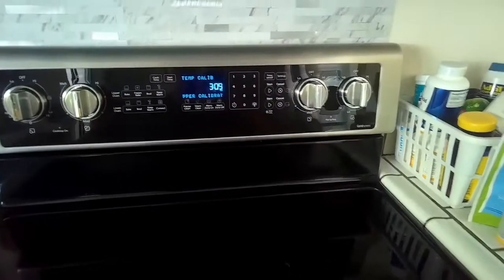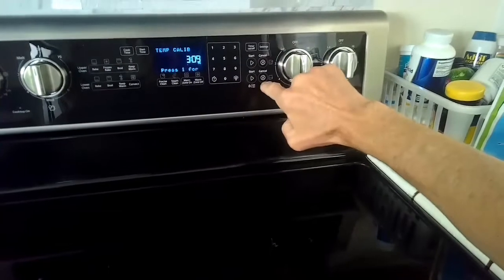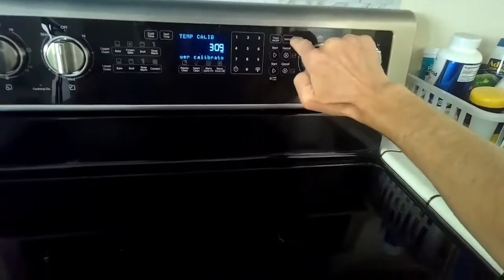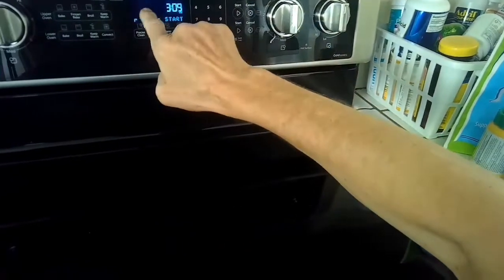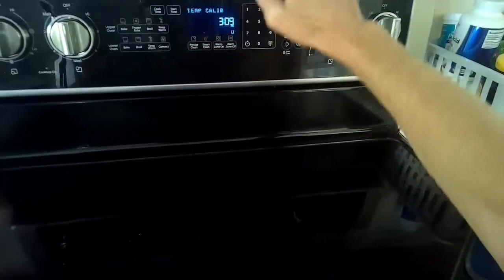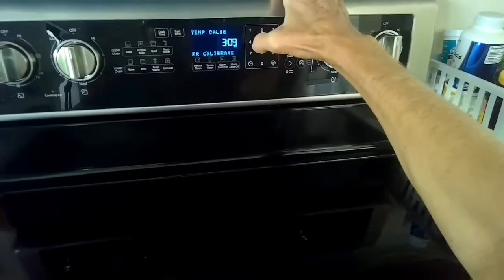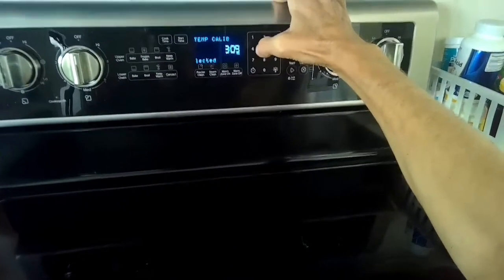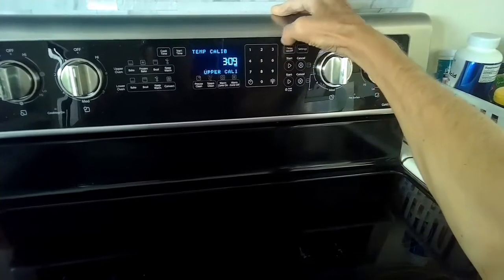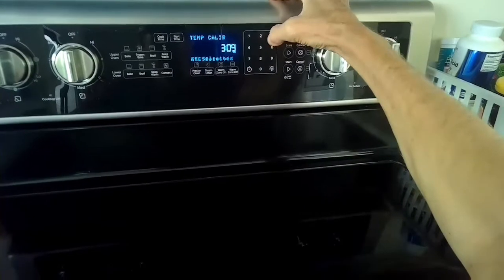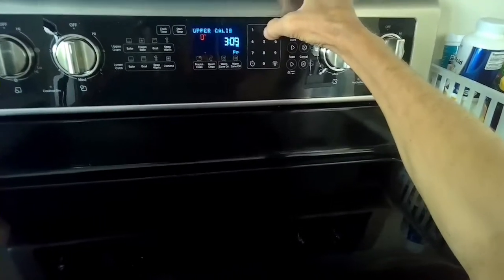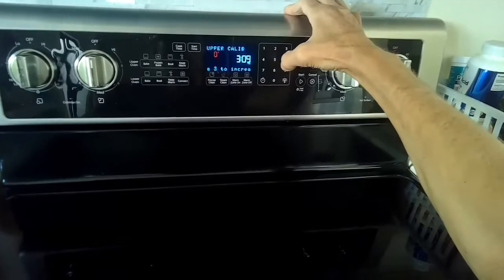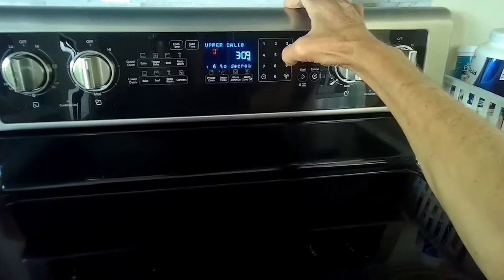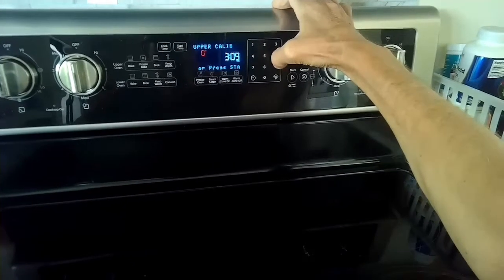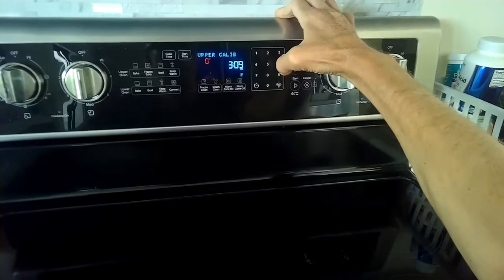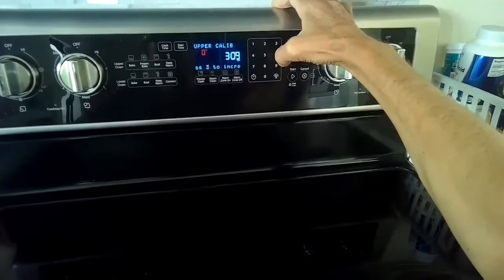For temperature calibration, just make sure you stop the baking cycle by pressing cancel, and then keep pressing the settings button right here until you get to one that says temperature calibration, and then it says upper calibrate selected. We want to go up by 25 degrees, so we're going to go to upper calibration. It says press start, press 3 to increase. Okay, let's do that.